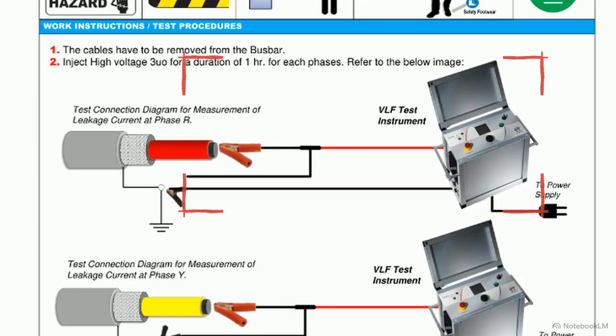Technicians inject a severe 3U0 high voltage into one phase at a time for a continuous duration of exactly 1 hour, while carefully monitoring leakage current trends for any symptoms of partial failure. The acceptance criteria are absolute: 0 dielectric breakdowns, 0 trips, and stable leakage current. Surviving the hour triggers a critical hold point, where a witness must formally approve the safe discharge of the phase and removal of the connections.